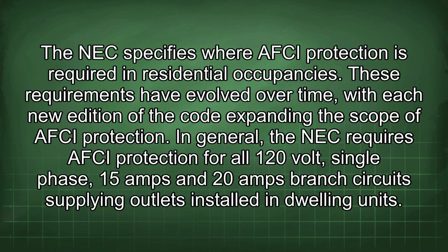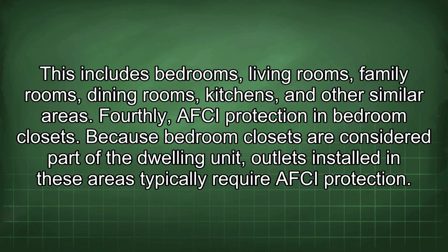The NEC specifies where AFCI protection is required in residential occupancies. These requirements have evolved over time, with each new edition of the code expanding the scope of AFCI protection. In general, the NEC requires AFCI protection for all 120-volt, single-phase, 15 amp and 20 amp branch circuits supplying outlets installed in dwelling units. This includes bedrooms, living rooms, family rooms, dining rooms, kitchens, and other similar areas.